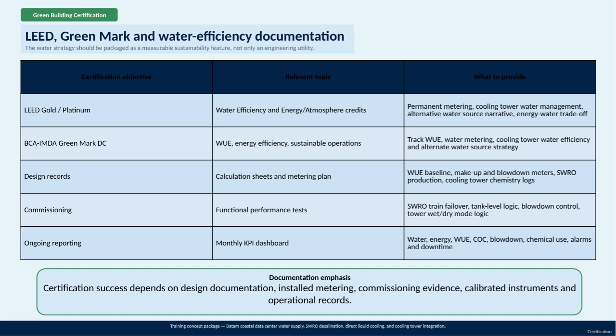Functional commissioning tests are equally important to verify that systems like SWRO failover and cooling tower controls operate correctly. Ongoing certification success relies heavily on monthly reporting via KPIs covering water, energy, water use efficiency, chemical use, and system performance indicators like alarms and downtime. Ultimately, documentation is the cornerstone of certification success. This means detailed design records, properly installed and calibrated metering devices, commissioning evidence, and thorough operational records must all be maintained consistently. Without this solid documentation foundation, achieving and maintaining certification becomes much more difficult.